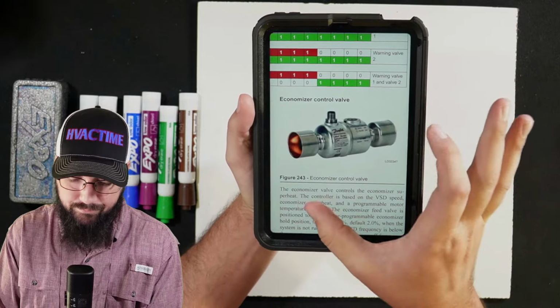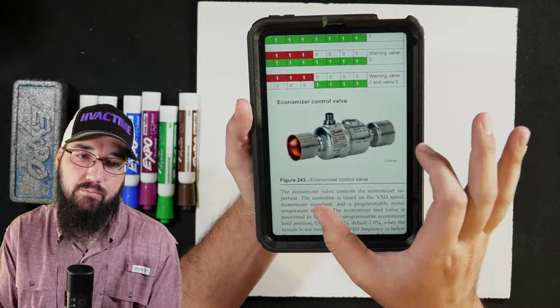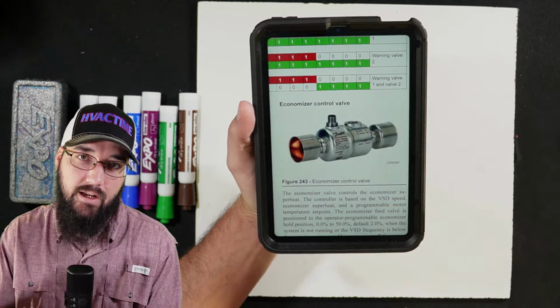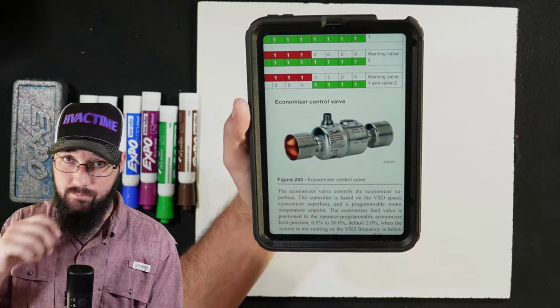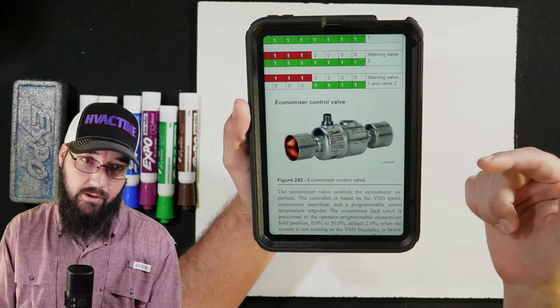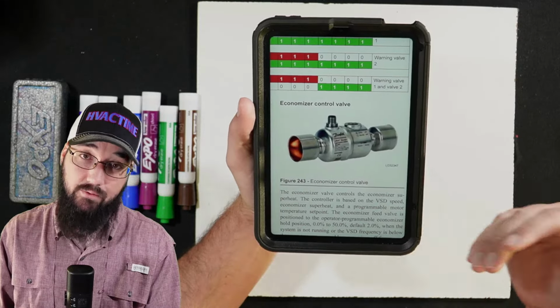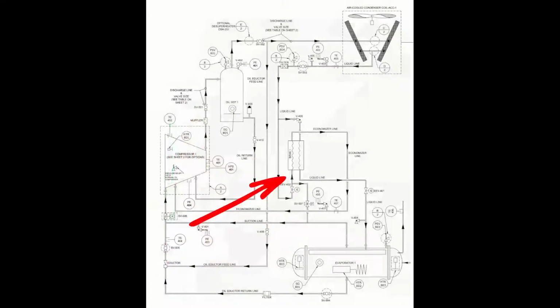You're going to see this little stainless steel module there in that liquid line feeding into the cooling circuit of the economizer, and then based off of superheat control, it will control how much feeds through that EXV and then back into the suction, or I'm sorry, back into the economizer port on this compressor. So this circuit does feed back into an economizer port separate from the suction line, so it doesn't come back to suction. And that is because we are still using an intermediate pressure.